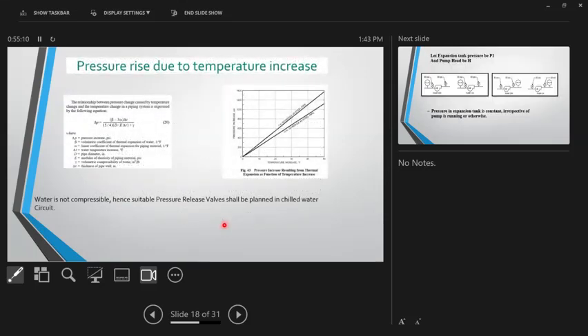Let's say you don't have an expansion chamber and it is a completely closed system. Then what happens? Now ASHRAE actually gives a beautiful equation for the relationship between pressure changes caused by temperature change. If you take a pipe of, let's say, 1 inch or 2 inch, close it from both ends and fill it with water, it is now an enclosed pipe, and you change the temperature. The temperature is changing, but there is no way for the water to expand. So its pressure would increase.